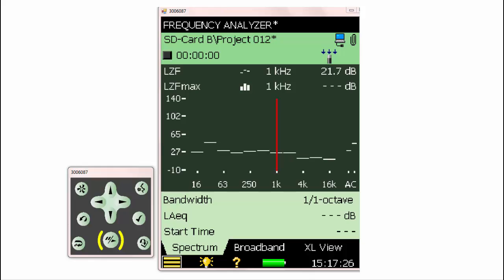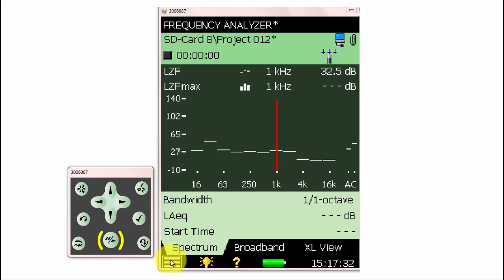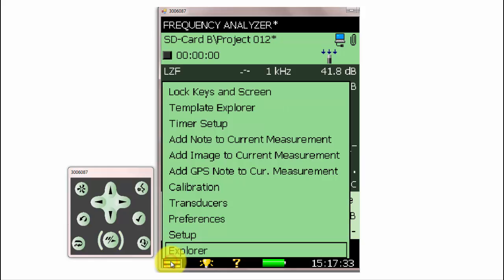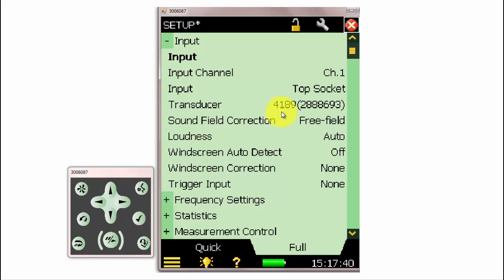The first thing we'll need to do is verify that we have the transducer selected correctly. We can go to the main menu at the lower left to select Setup. In the input section, we can verify that the transducer is properly selected with its serial number and that we have the correct input selected.